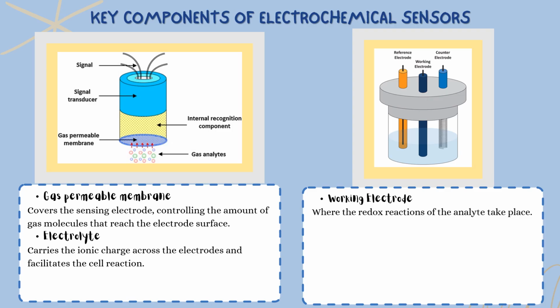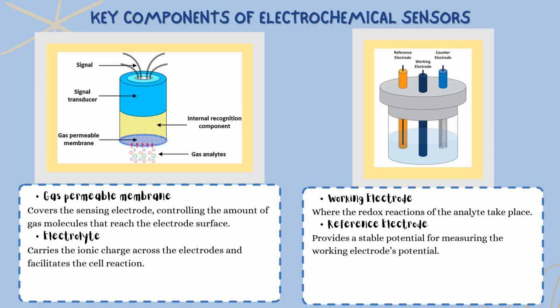The working electrode is the primary site of the redox reaction, where the target analyte interacts and produces an electrical signal proportional to its concentration. Positioned near the working electrode is the reference electrode, which provides a stable and fixed potential to serve as a baseline for accurate measurement. Completing the system is the counter electrode, positioned opposite the working electrode. This electrode allows electrons to flow and balance the current generated at the working electrode, ensuring continuous redox activity.